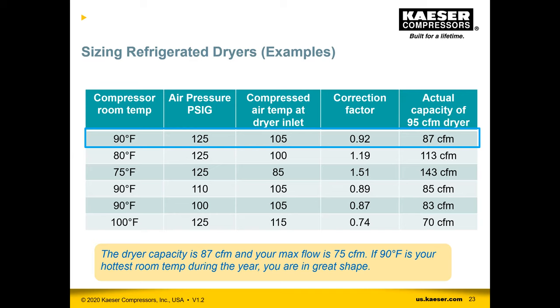The other lines on the chart show how you'd adjust drying capacity under different temperature conditions and pressures. If you dropped room temp another 10 degrees, that 95 CFM dryer could handle an even larger compressor flowing through it. The correction factors are really important to make sure you've selected the right dryer.